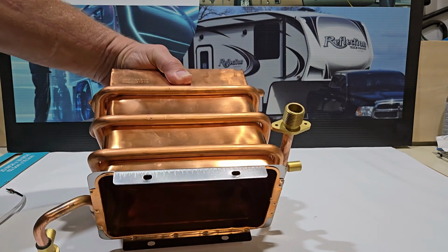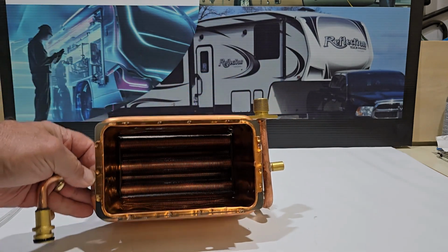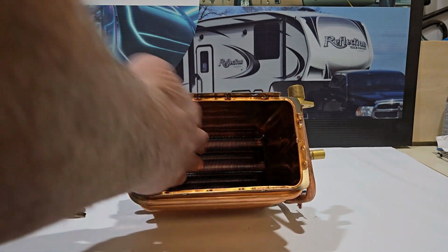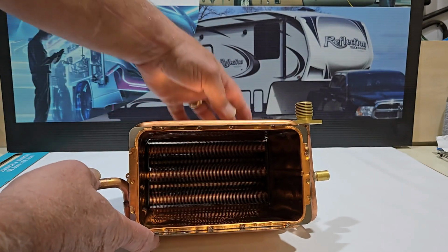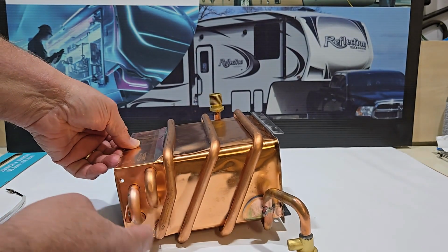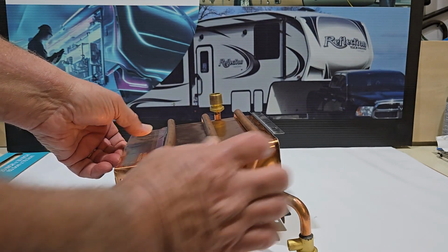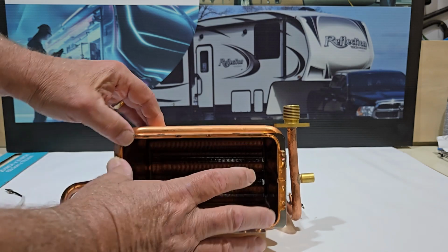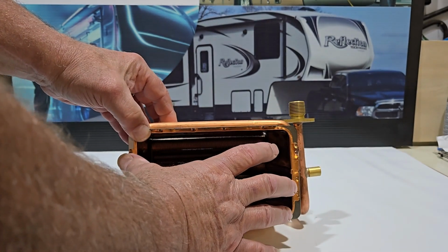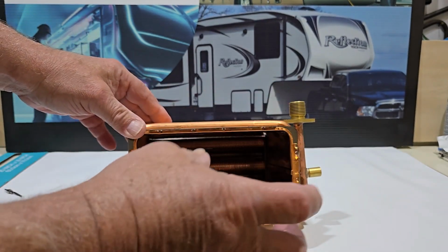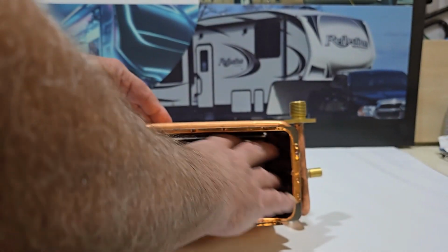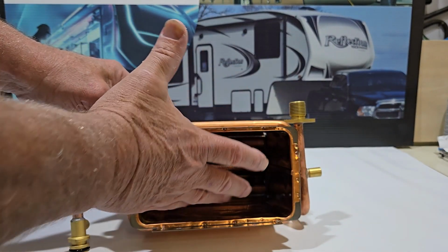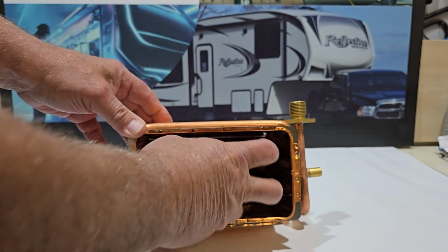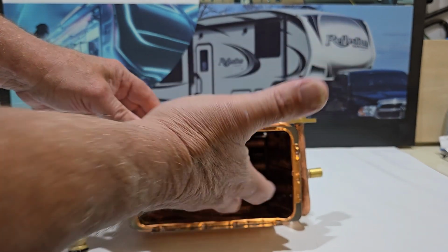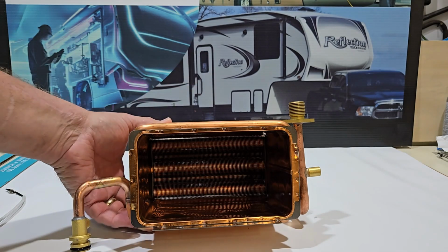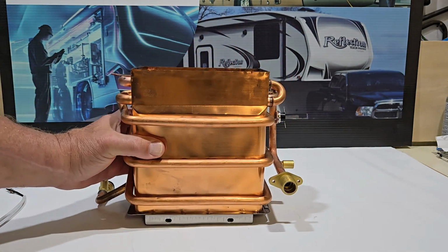Let's take a look at the bottom of this. You can see that this heat exchanger is mostly just an empty cavern, with the coils of copper tubing only taking up the top section. Most of this acts like a flue, where our burner sits down here and that hot air travels through here. It gets superheated as it comes off the flames, and our burner assembly directs those flames up towards where the actual heat exchanger part is, at the top.